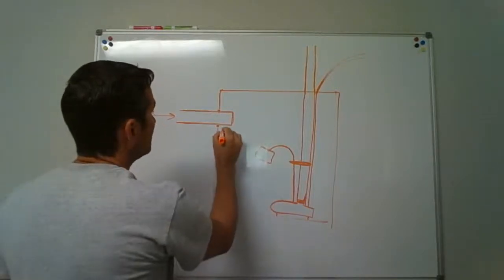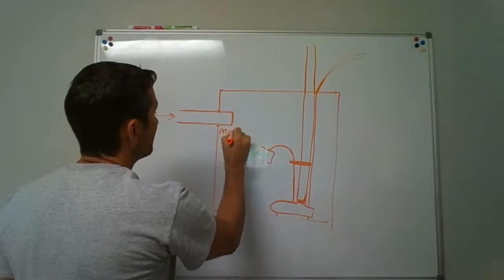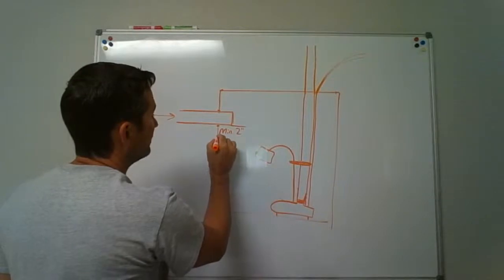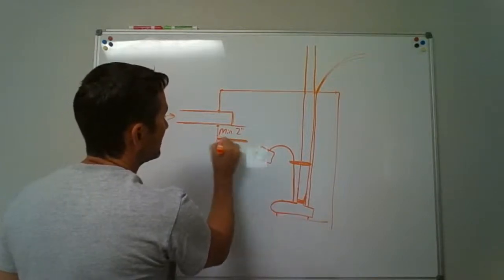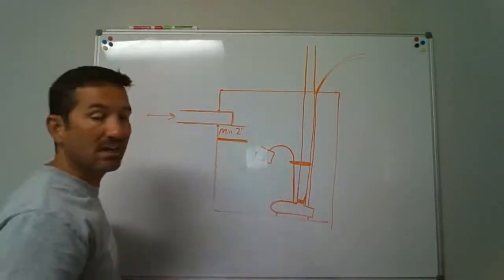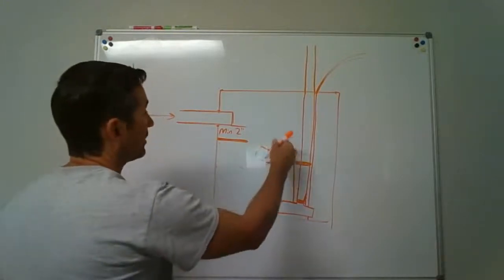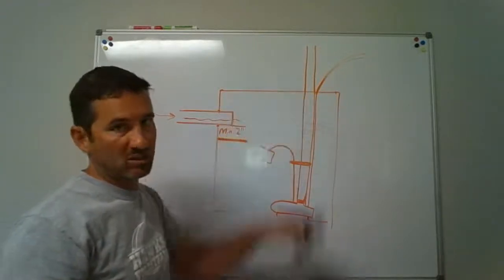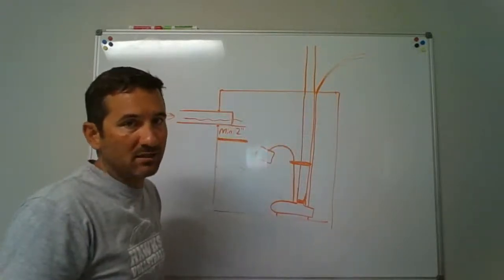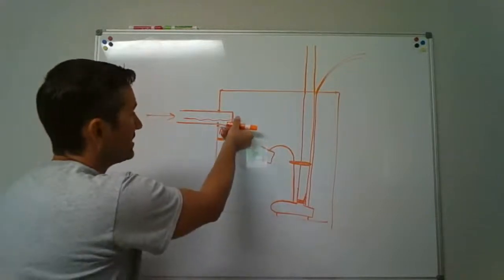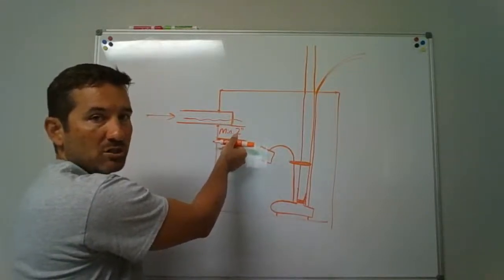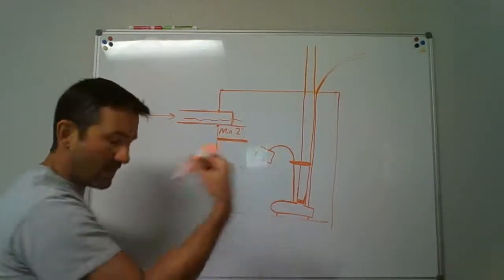They say you should allow at least a minimum of 2 inches between the bottom of this pipe where it's coming in and where the level is set for that thing to kick on and get pumped out. We do not want stuff backing up into this pipe because we've got the float switch set way too high, to where it's not kicking on until it starts to back up. So give yourself at least 2 inches between where everything dumps in and where the pump ought to kick on, okay?